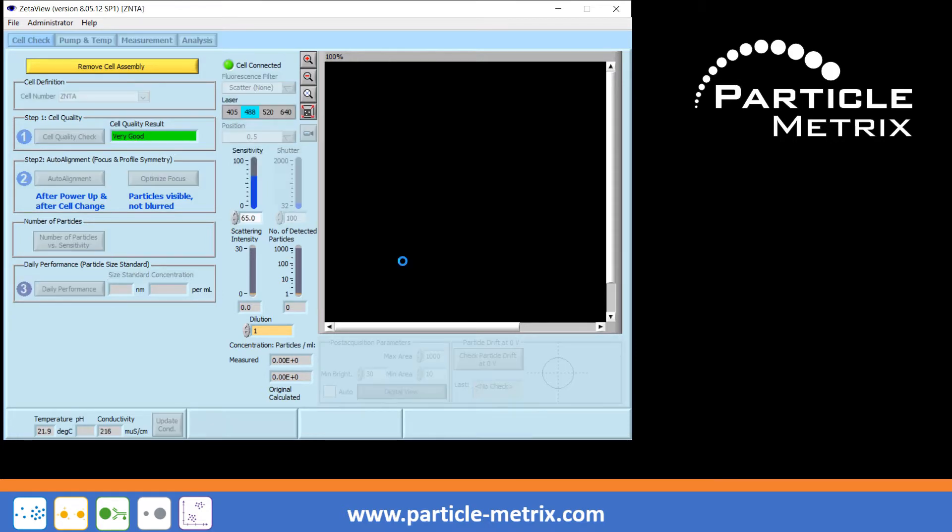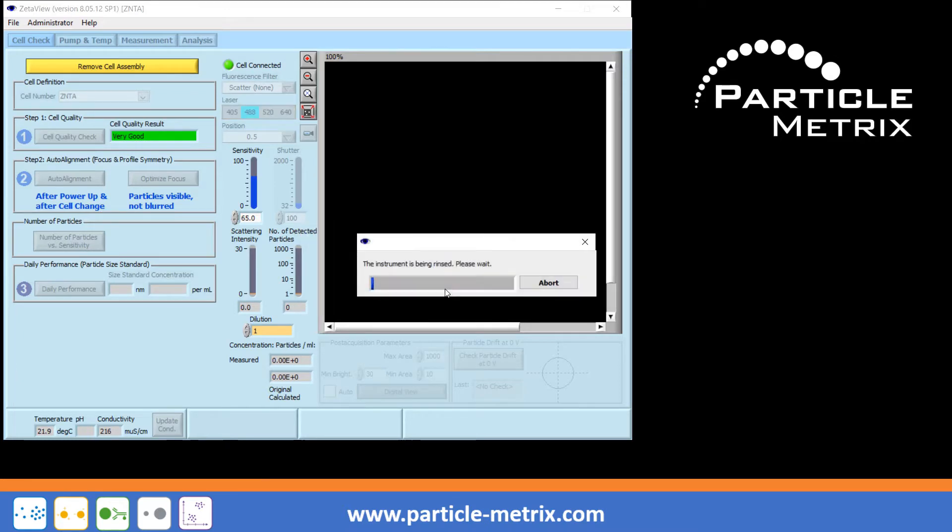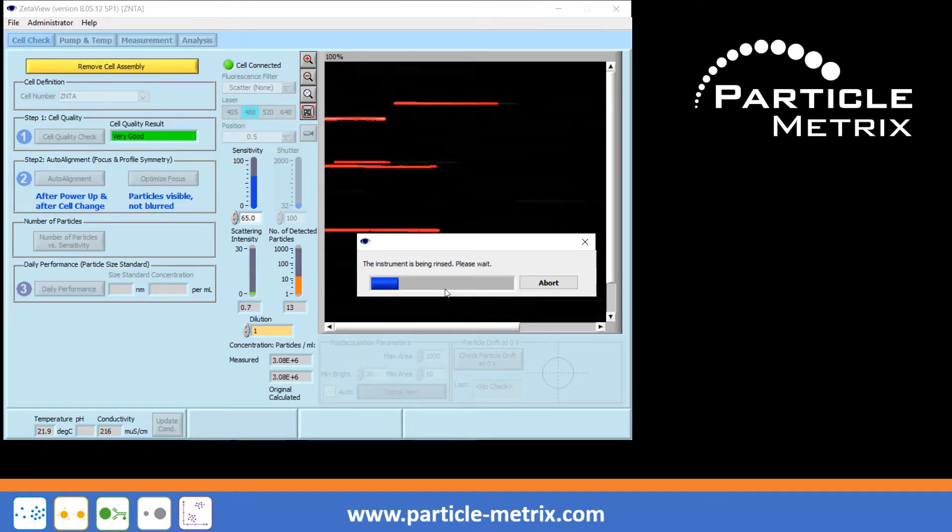Once the initialization is finished, select the appropriate pump for rinsing the fluidic system of the ZetaView with water. The corresponding water reservoir should be filled with particle-free water, such as MilliQ water or similar, to avoid excessive number of particles during the cell check.